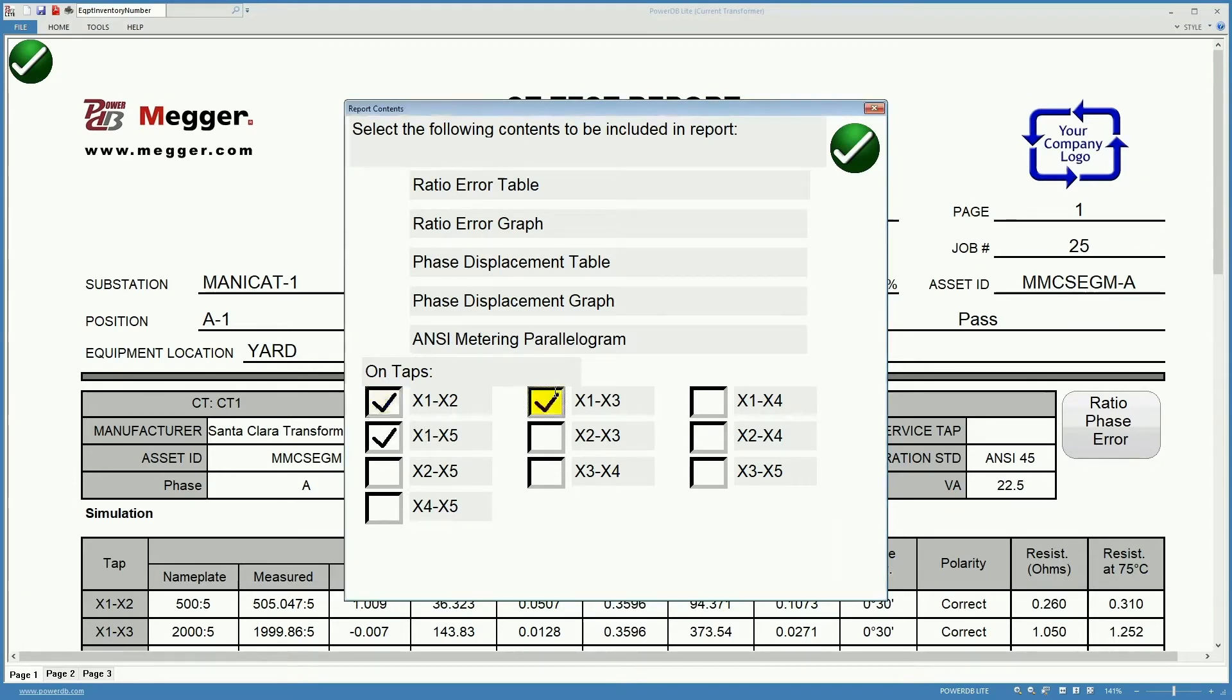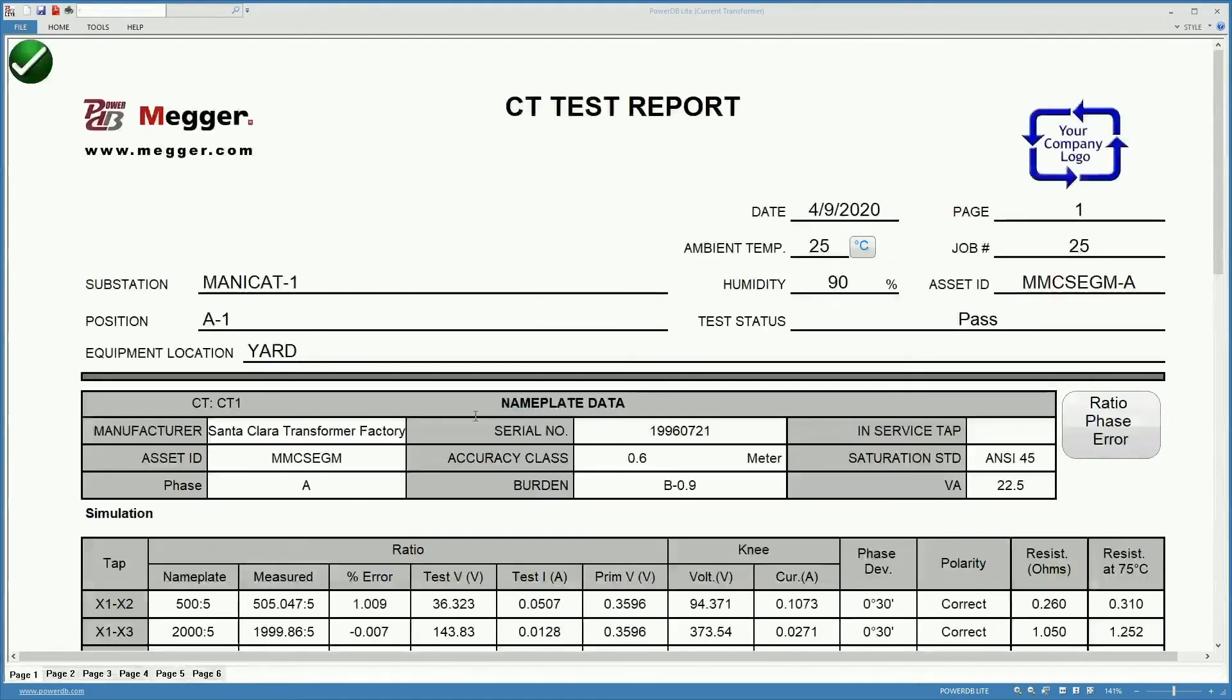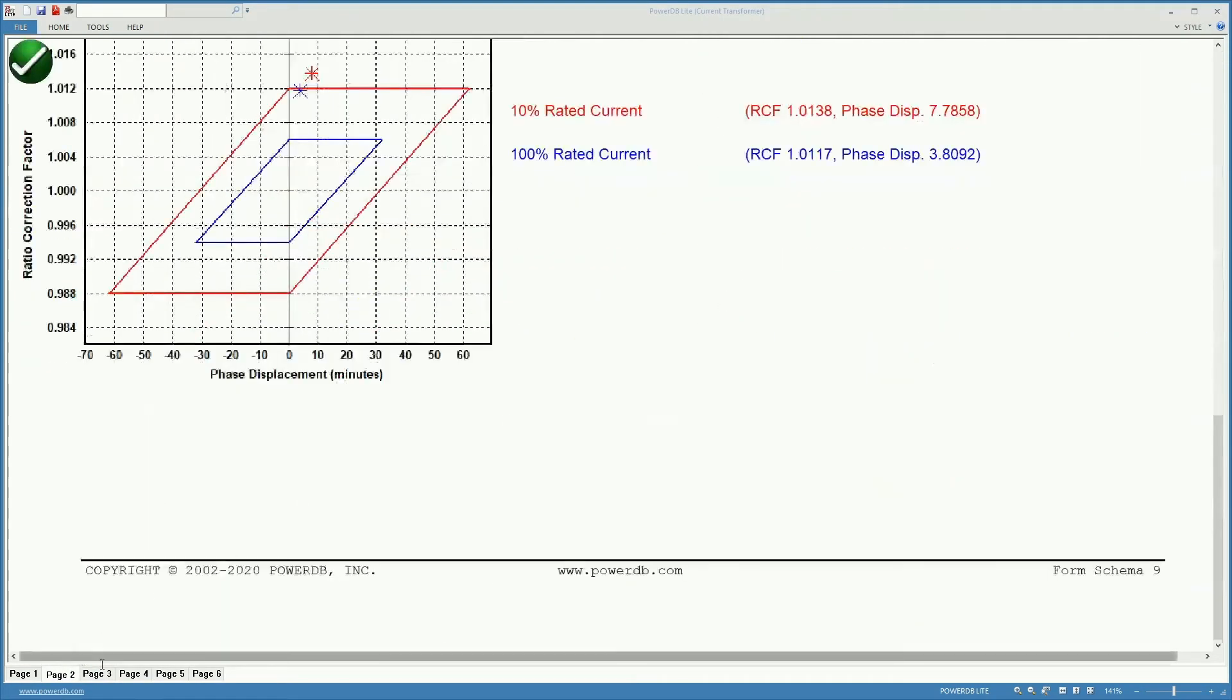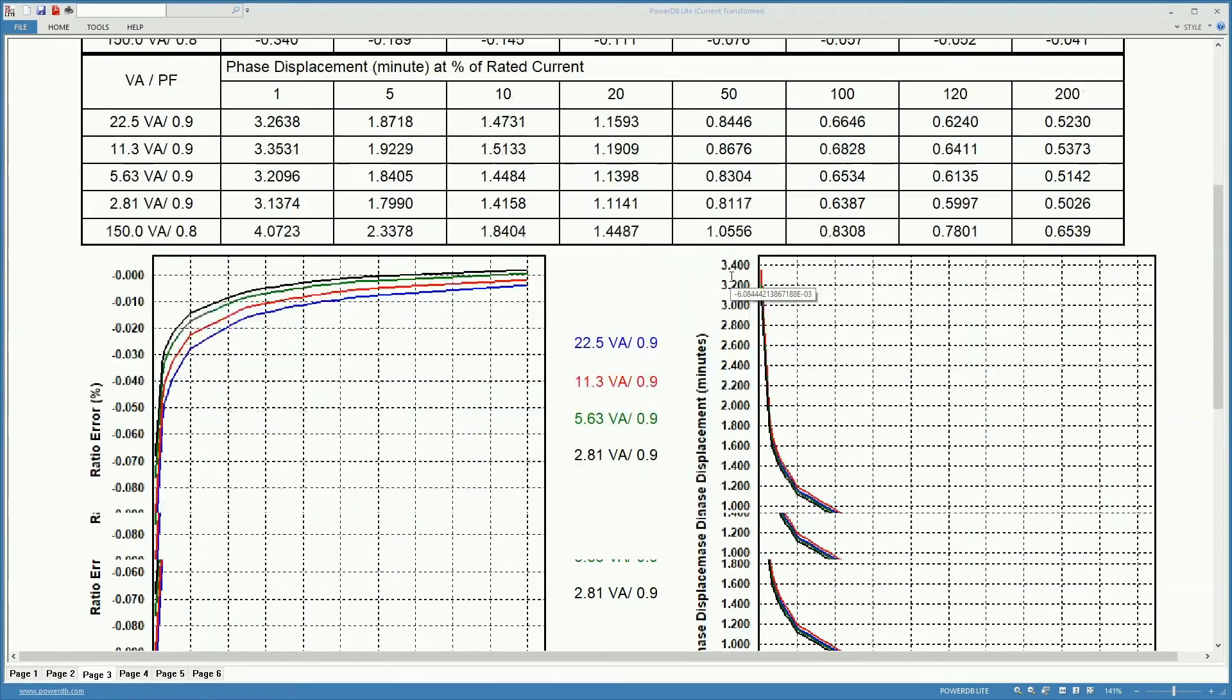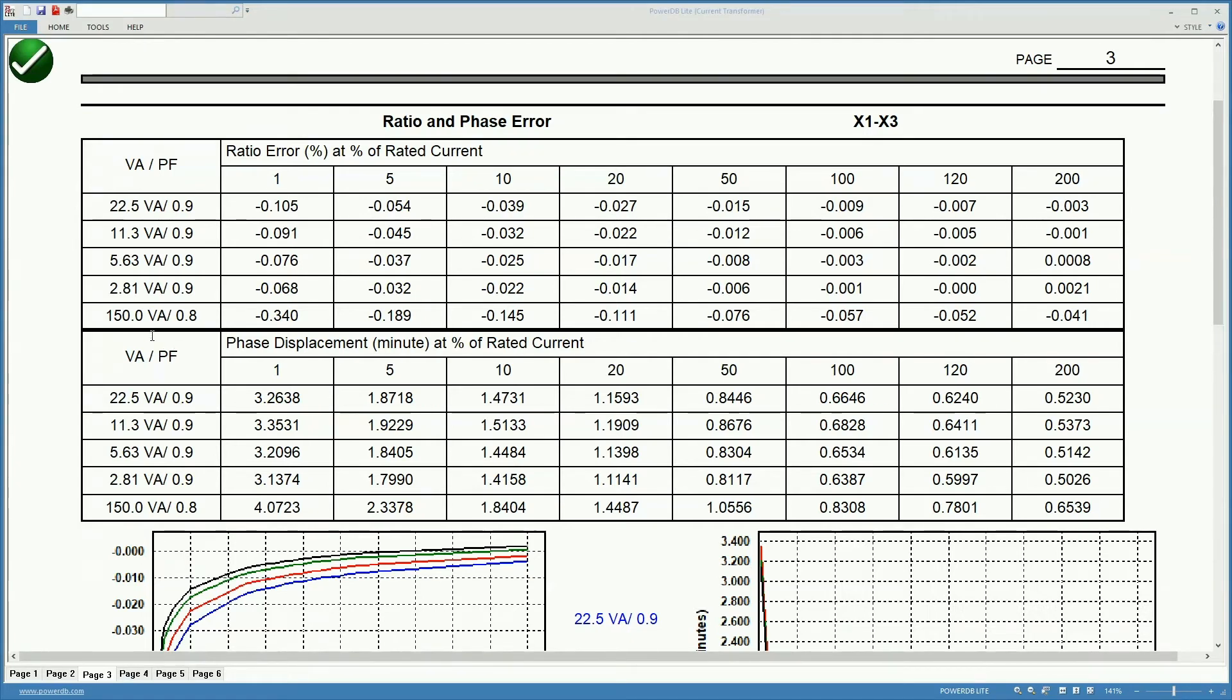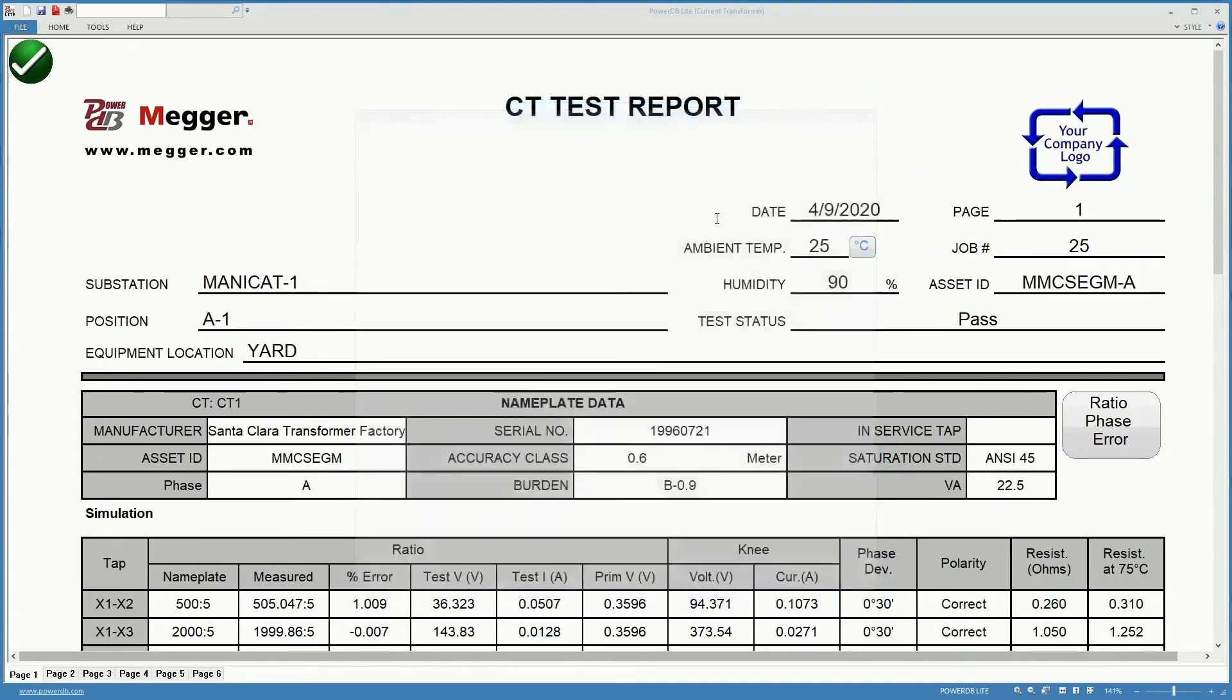For example in this case for clarity we only selected X1 to X5. We could select let's say all the X1, the one that I have called primary tabs, or we can do it for the auxiliary or secondary tabs like the X2, X3, X2, X4, etc. The more tabs we select here, the longer the report will be. It will also be a more complete report because it will contain more information for each of the different individual tabs and it will contain the ratio and phase error, the phase displacement error.